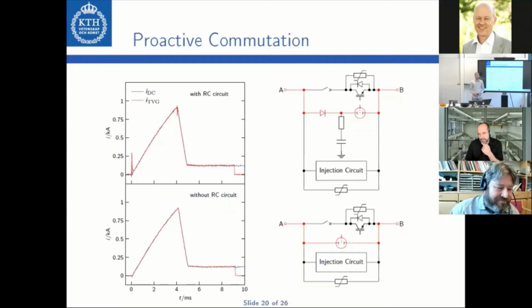That being said, in vacuum we often talk about vacuum interrupters, the mechanical switch, which are used in medium voltage applications because of the non-linearity of the dielectric capability. But for this kind of arrangement, the non-linearity is not such a hurdle since there is no mechanical movement, so one could just move the electrodes further apart. The only downside would be that a higher triggering voltage would be needed to cause the initial discharge in the triggered vacuum gap.